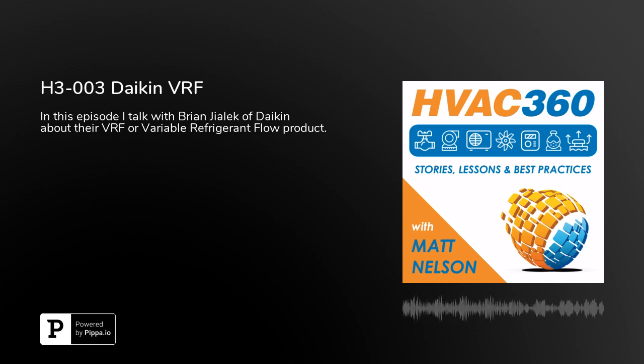Sure. Now, one question I've seen is, if I'm ducting directly to the unit, what kind of air should I be ducting directly in? Should it be tempered? It depends on the application, of course, and what part of the country you're in. South Florida is going to be very different, obviously, than British Columbia. So in most applications, what I'm going to try to do is achieve a neutral air that I'm ducting to those indoor units, maybe in the range of somewhere between the high 30s to the 60s, maybe even higher. The ducted outdoor unit will take a range that's much higher than that.